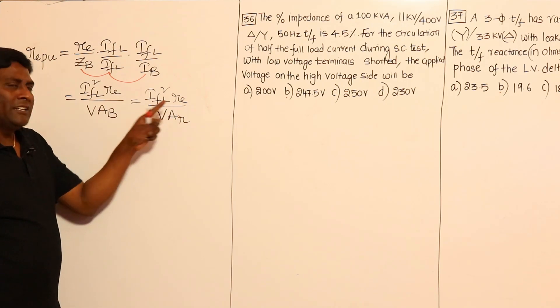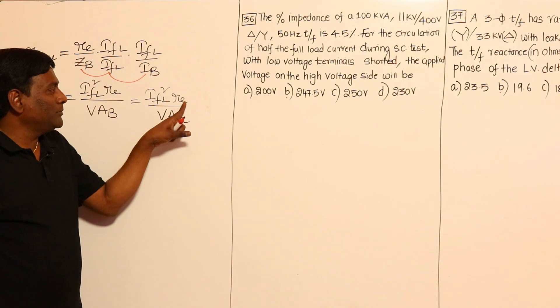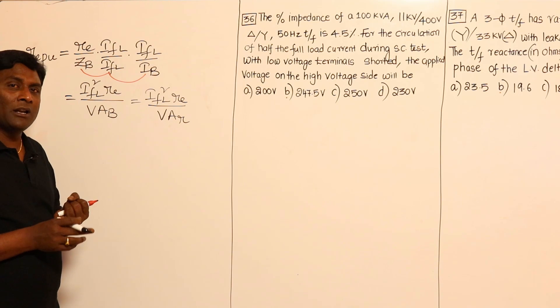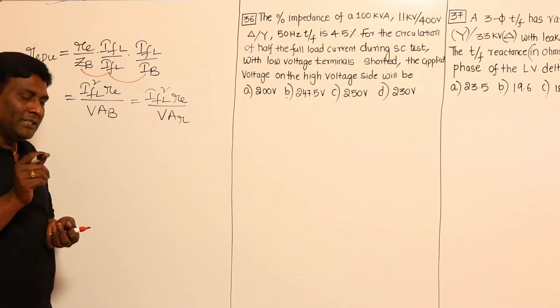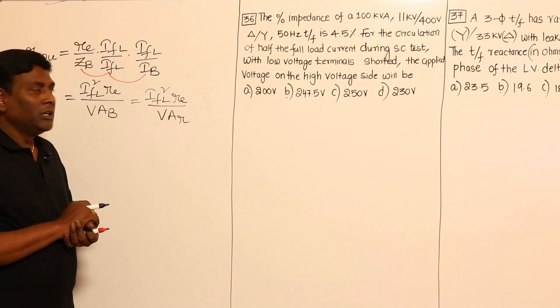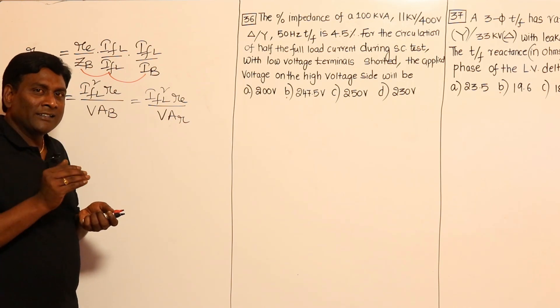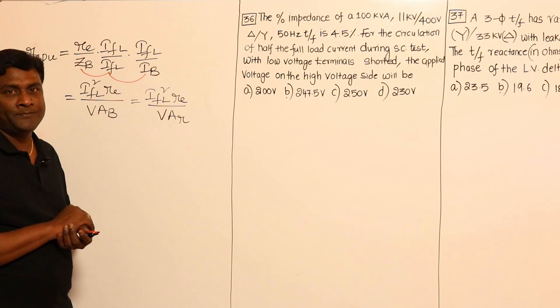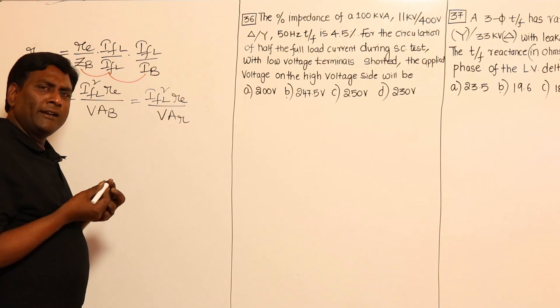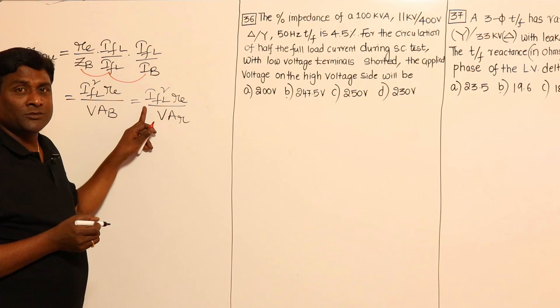Now, IFL² × Re — full load current squared multiplied by equivalent resistance — is nothing but full load copper losses in the windings. In the SC test you get copper losses. But the SC test can be conducted at less than full load conditions also, so we have to check whether the SC test is conducted at full load or not. If not, we have to map it to full load. IFL² × Re is the watt meter reading in short circuit conditions, which equals full load copper losses.